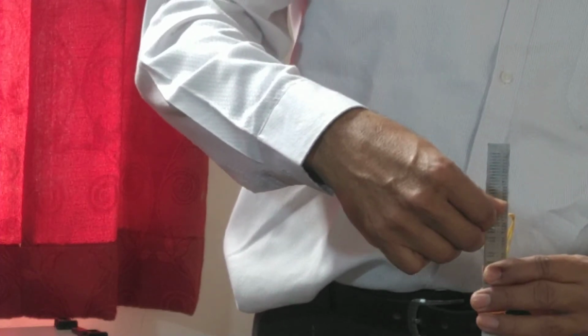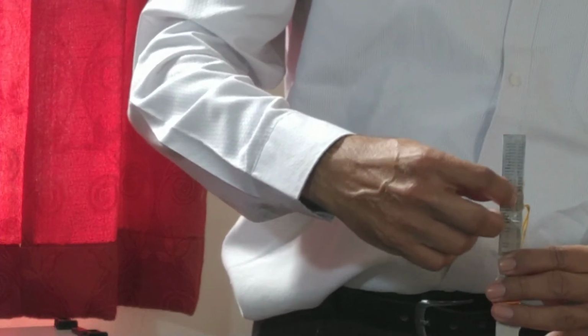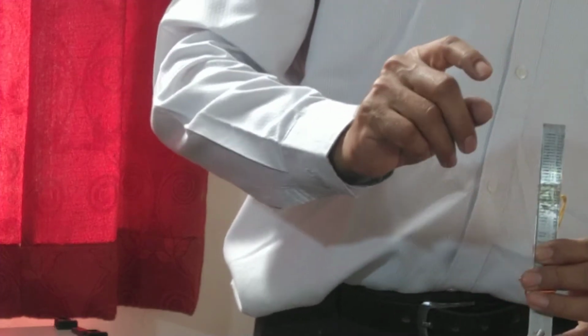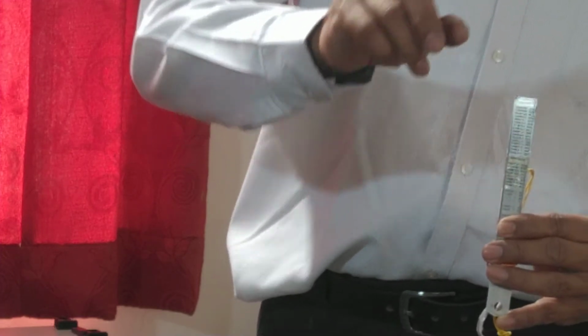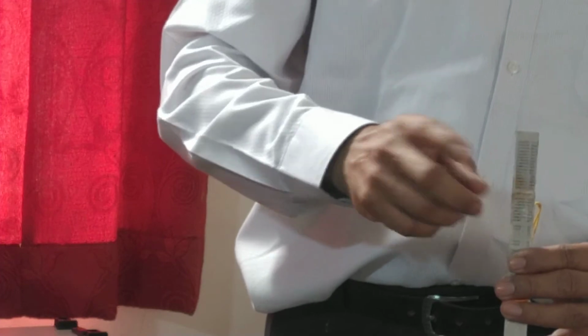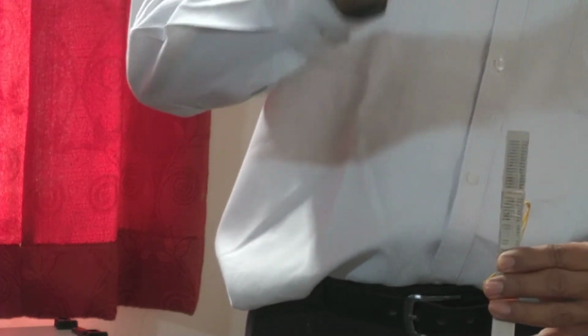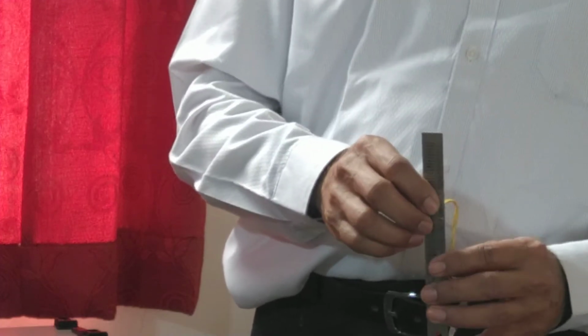Even if I scrub the strain gauge, even if I apply pressure on it, the resistance should not alter. If the resistance is altering, that means the strain gauge is not properly mounted. So these two checks are needed for checking proper mounting of the strain gauge.